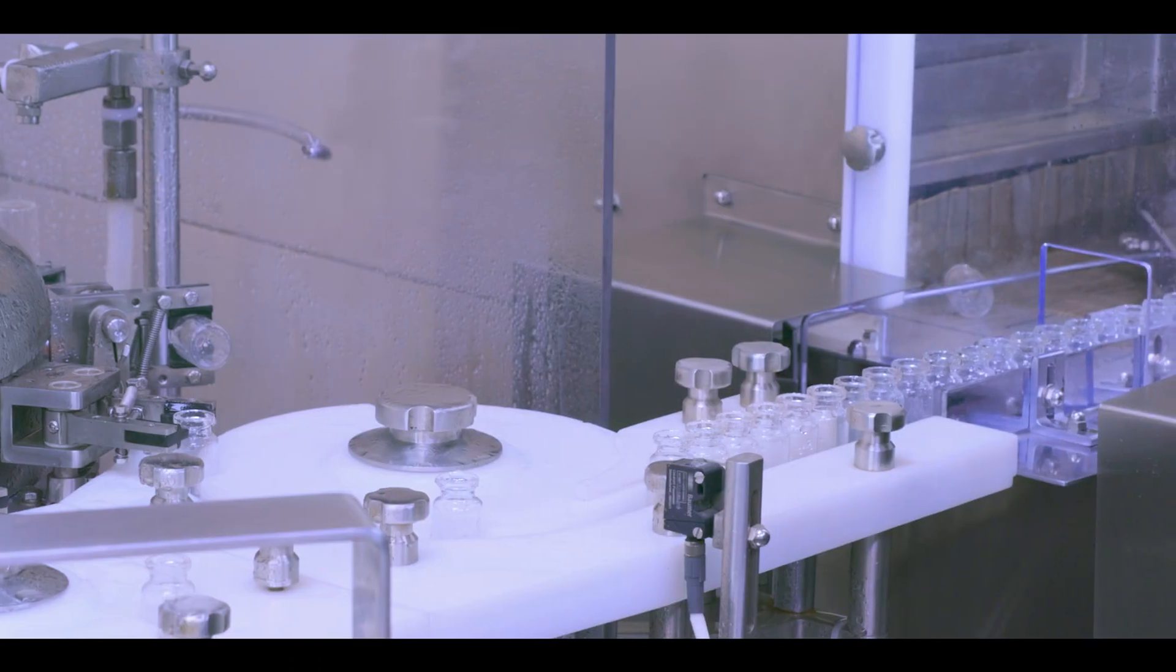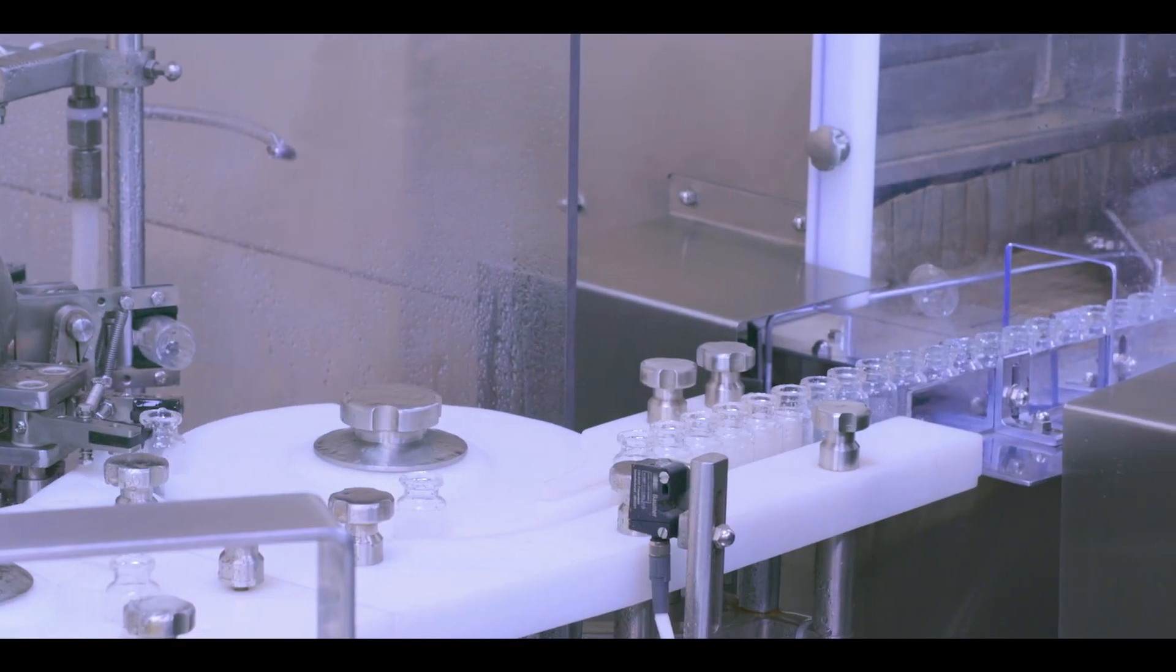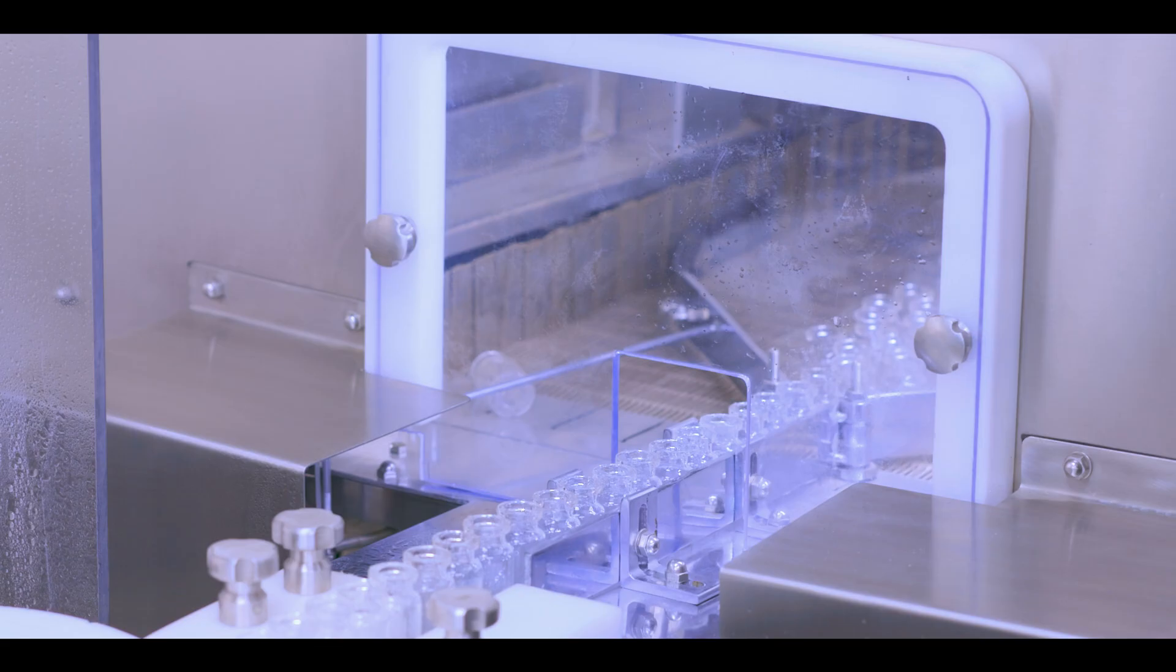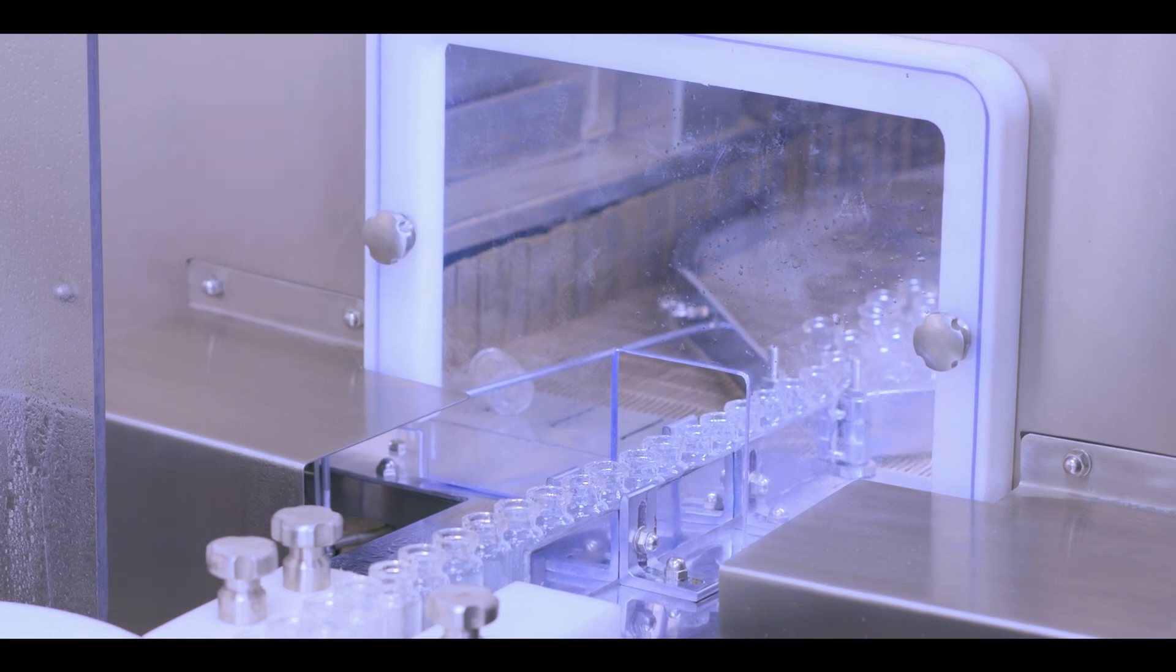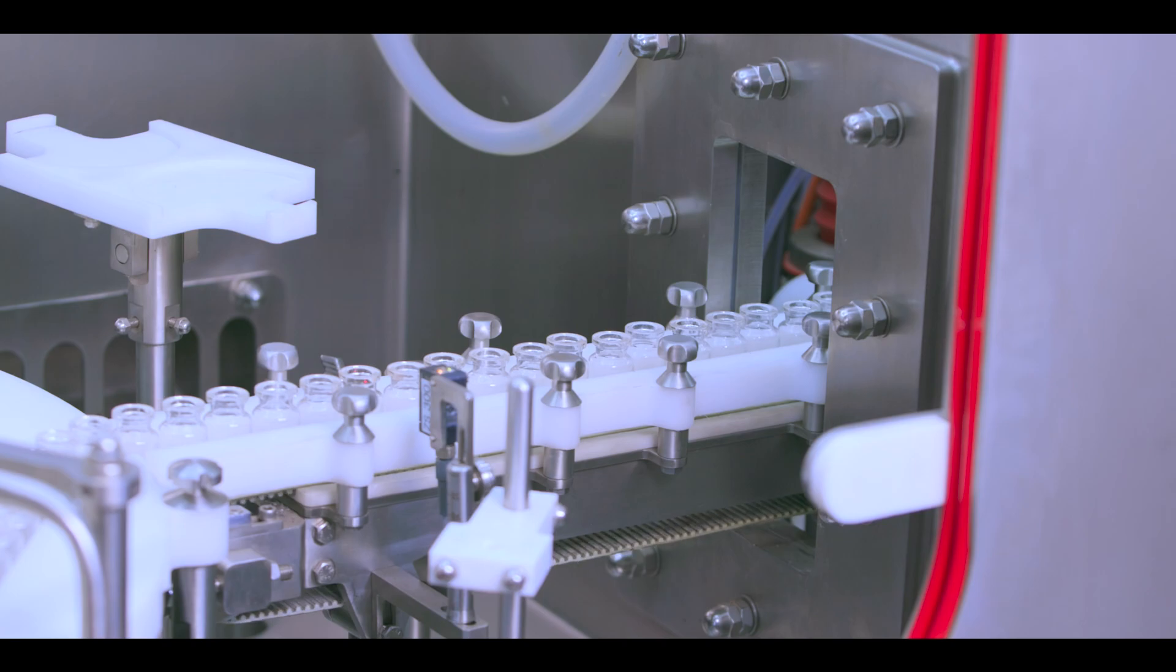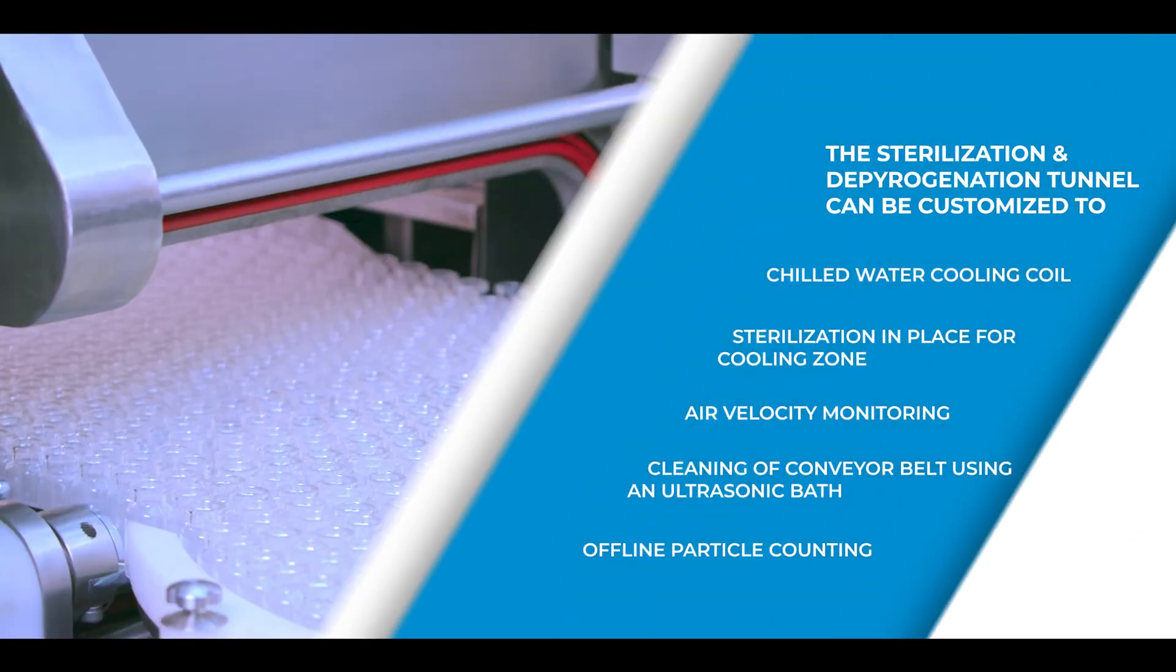The sterilization and depyrogenation tunnel includes a drying zone, a hot zone, and a cooling zone. The vials are depyrogenated by heating them to a temperature more than 300 degrees Celsius.